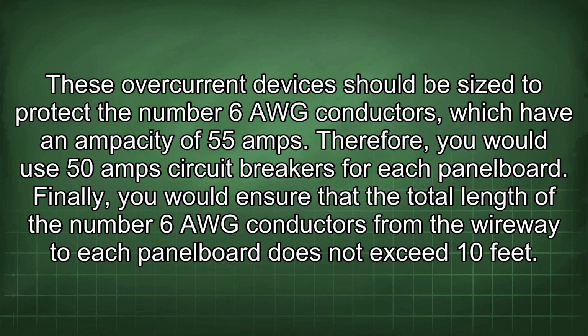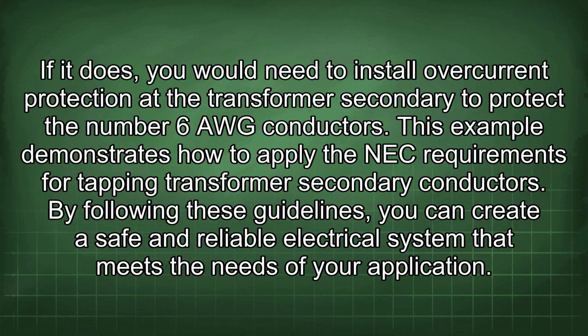Finally, you would ensure that the total length of the number 6 AWG conductors from the wireway to each panel board does not exceed 10 feet. If it does, you would need to install overcurrent protection at the transformer secondary to protect the number 6 AWG conductors. This example demonstrates how to apply the NEC requirements for tapping transformer secondary conductors. By following these guidelines, you can create a safe and reliable electrical system that meets the needs of your application.